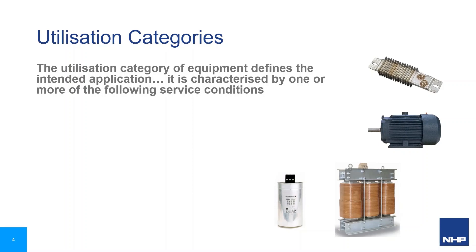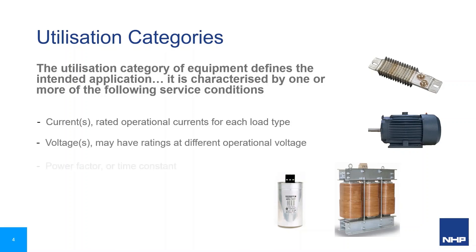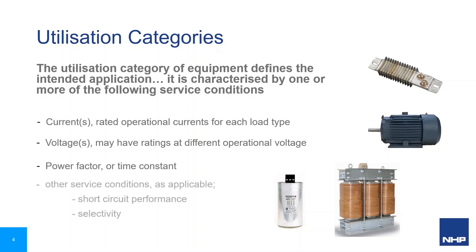With each load type having a different current profile during making and breaking operations, different utilisation categories are prescribed for major load types for on and off switching functionality. A device can be suited for different applications, hence can have different rated operational current values for different utilisation categories. A device's operational current for a utilisation category may also be different at different operational voltages. There are categories for AC switching and for DC switching. A switchgear device usually has ratings stated for several utilisation categories for the different applications, with different rated operational current values.